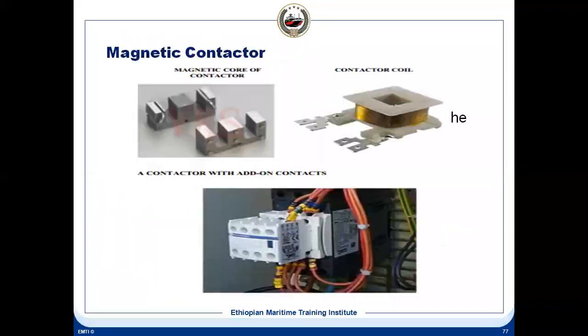Yes. You can see. Okay, so this is a magnetic contactor. Why do we call it a magnetic contactor? Because it has got a coil inside. Normally, whenever you have problems with the starter, you'll find this coil sometimes gets burned or the insulation of the coil drops. So you need to check the ohmic value of this coil winding. When it becomes weak, it will not operate the contacts. So that is the reason it is known as a magnetic contactor.